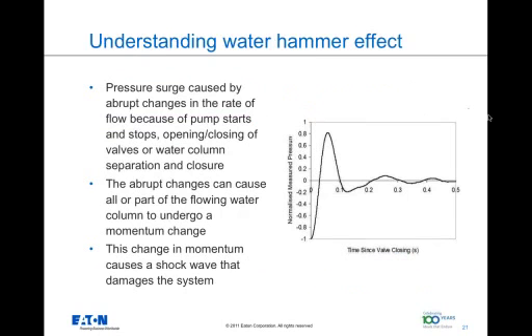Let's understand a little bit about the water hammer. In a typical pumping system, the pressure surges are caused by changes in flow because of pump starts, stops, opening, closing of valves, water column separation, and closure. Pressure surges lead to sudden changes in momentum of the water column. This momentum change creates a shock wave that causes damage to the piping system. Such shock waves can damage the system and reduce its life. This can happen during the ramp up or ramp down period of the pump. This phenomenon is called water hammer, and it causes significant damage to the check valve and surrounding pump system.